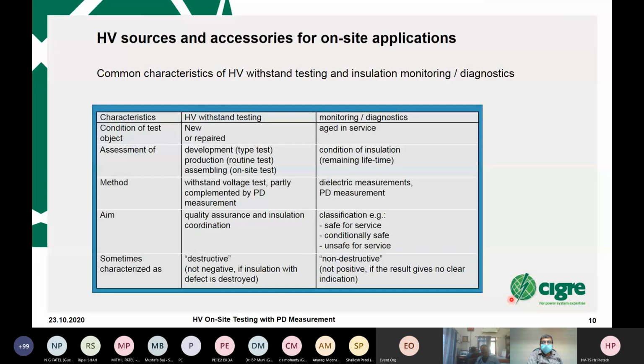Now, coming back to my presentation, which is part of the technical brochure. As I mentioned, first we have to see what kind of high voltage source we can deliver on site. And there you have to distinguish between the so-called withstand testing, normally 1 minute, with an increased voltage level. This is done during type testing, routine tests, and so on. These values are described by the relevant standard for cable, for GIS compartment, and so on. And this is normally required, or at least said to be a complementary addition, is PD measurement, and the aim is to assure the quality which I mentioned. Sometimes it's destructive. For example, if you have a transformer and you apply lightning impulse, which is part of it, but this is not the intention of today.